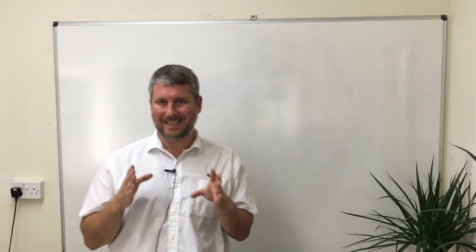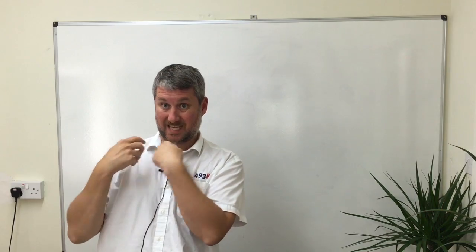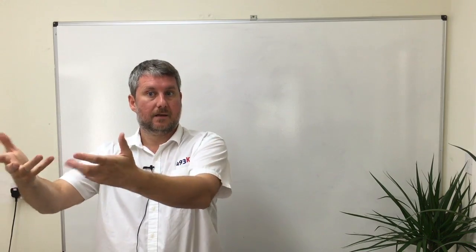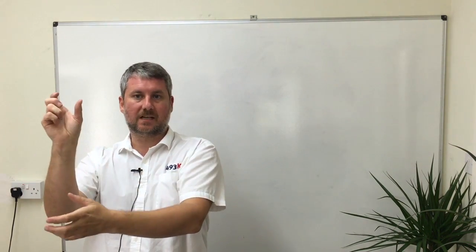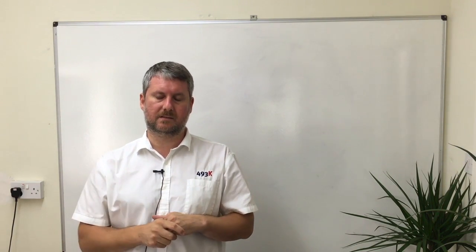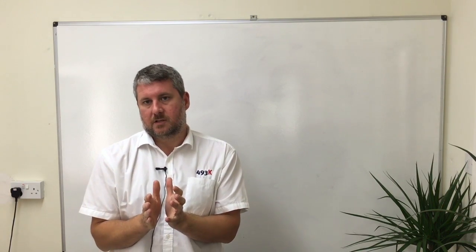A lot of machinery integration software takes our data, which we send every 2 seconds, and averages that over a period of time, and then passes that single value onto the machine to control, which is the correct and the right way to do it, because the machine doesn't need to see every temperature signal every 2 seconds. 10-15 seconds is enough time to send the data on. So what the machine integration part of the system is doing is averaging and looking for erroneous data and removing that.